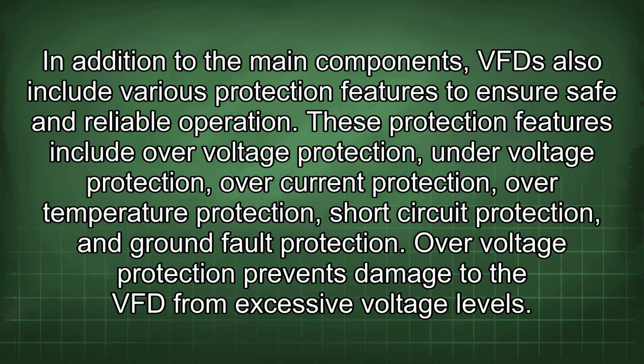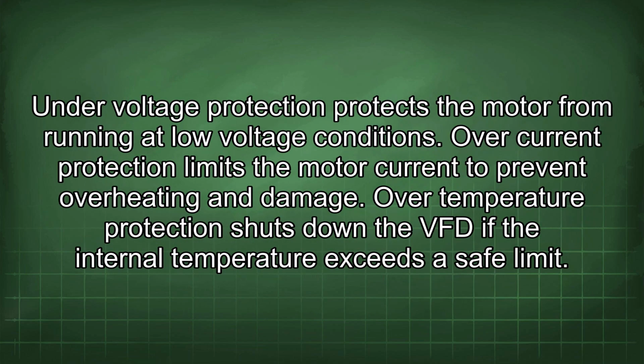In addition to the main components, VFD also include various protection features to ensure safe and reliable operation. These protection features include overvoltage protection, undervoltage protection, overcurrent protection, overtemperature protection, short-circuit protection, and ground fault protection. Overvoltage protection prevents damage to the VFD from excessive voltage levels. Undervoltage protection protects the motor from running at low voltage conditions. Overcurrent protection limits the motor current to prevent overheating and damage.